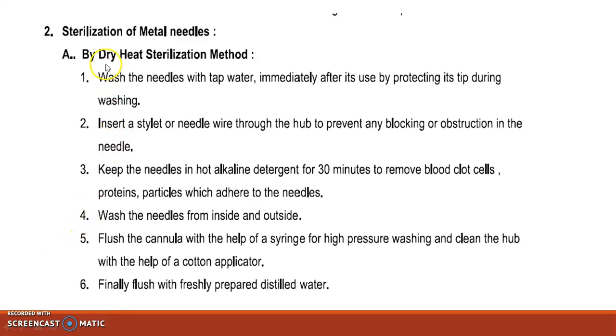Now, sterilization of metal needle by dry heat sterilization method. Wash the needle with tap water immediately after it is used, protecting its tip during washing. Insert stylet or needle wire through the hub to prevent any blocking or obstruction in the needle. Keep this needle in hot alkaline detergent for 30 minutes to remove blood clots, cells, proteins, and particles which adhere to the needle. Wash the needle from inside and outside.